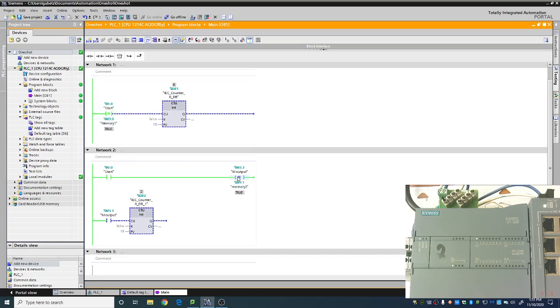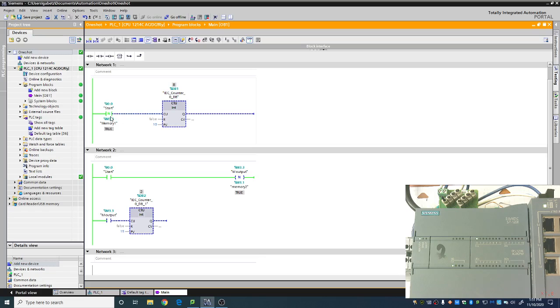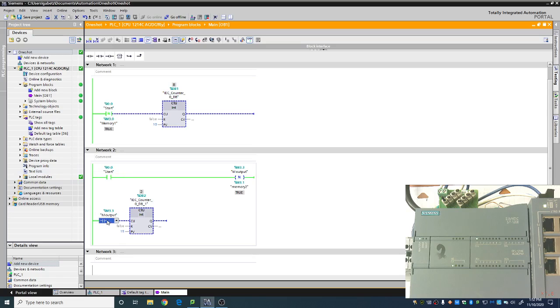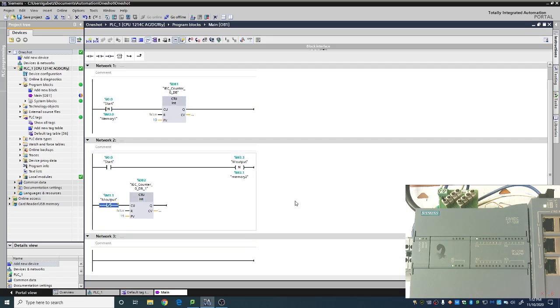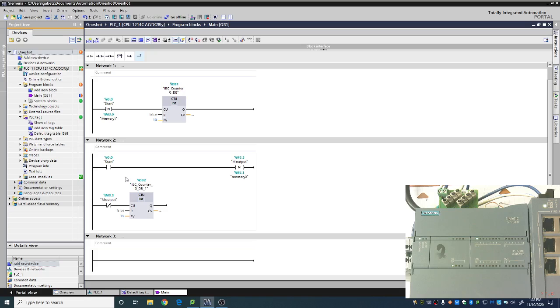Now, using the output as the one-shot does give us some slight benefits. It allows us to actually invert the logic of it. Imagine you want to do a one-shot that would stop something, stop the conveyor belt or whatever the case is. Well, if you want to have a stop button, you need to have that basically normally closed. The one-shots as an input are always going to be normally open, so they're normally going to be makes. So we can't use it as a stop button directly. We'd have to do something like this, where we're going to have multiple inputs on here that we can then have an output. And then we can take the inverse of that. So I could make this a break contact here instead. And that is a wonderful capability for us because it allows us to do the opposite of a one-shot. It's still detecting that transition, but it's breaking the logic instead of making the logic. So there is a time and a place for using an output like this as well as an input. You can always use an output instead of an input.